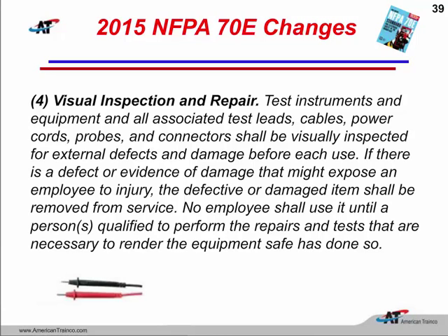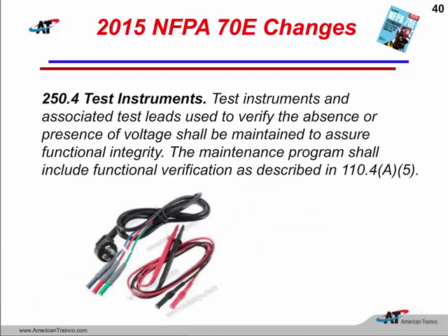If there is, let's say, a malfunction with that meter, it's going to have to be removed from service immediately, and it is going to have to be sent back to the manufacturer to be calibrated again and repaired so that we can use that particular meter again. So it's very important that we're doing maintenance with our meters and test leads. They're going to want to make sure that we do this once every 3 years. We're going to have to document that this has been performed. The meter is really the only tool in our hand that we can establish that electrically safe work condition with. Extremely important that we maintain it according to the manufacturer's instructions.